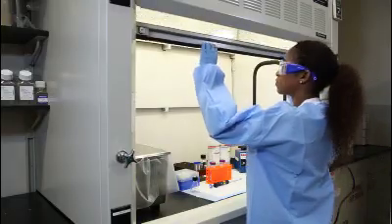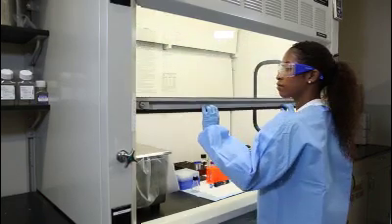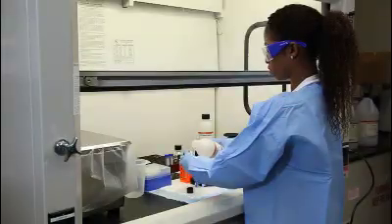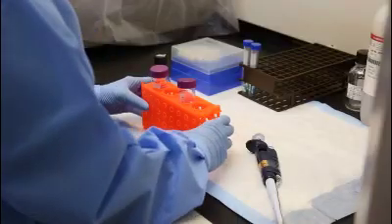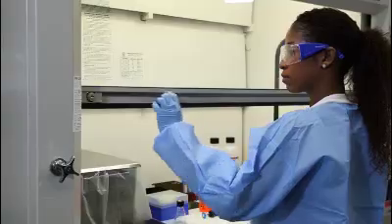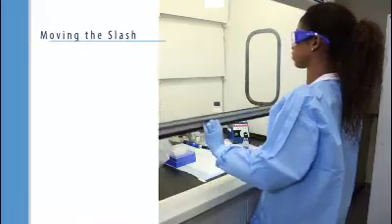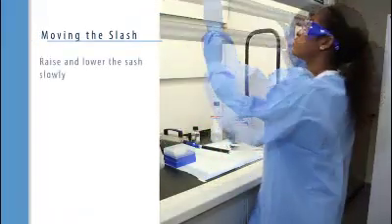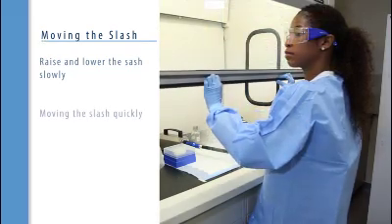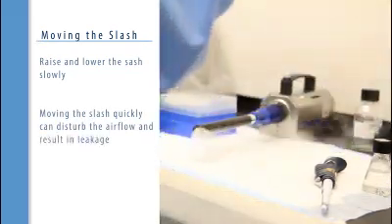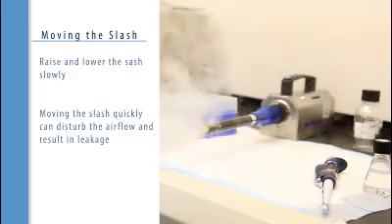Sash height is important for maintaining proper airflow and to keep those working in it and around it safe. When working in the hood, the sash should be at the certification mark. Raising and lowering the sash should be done slowly. Moving the sash quickly can disturb the airflow and result in leakage.